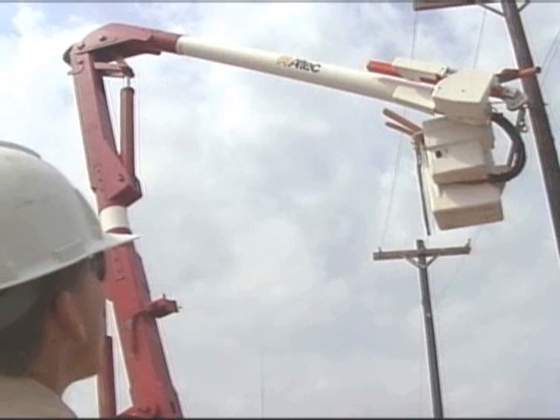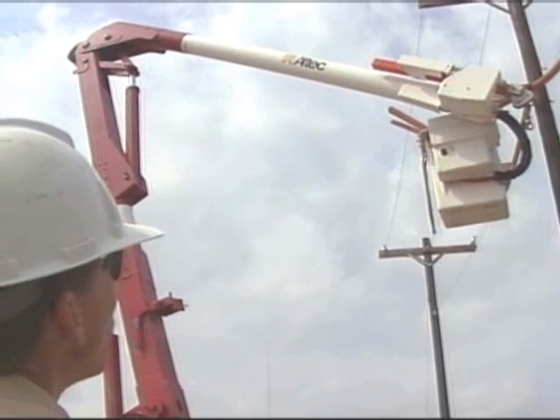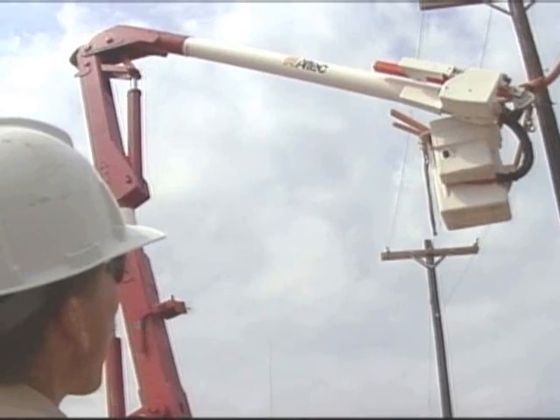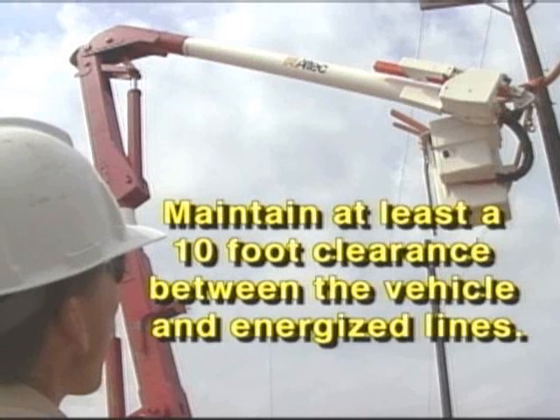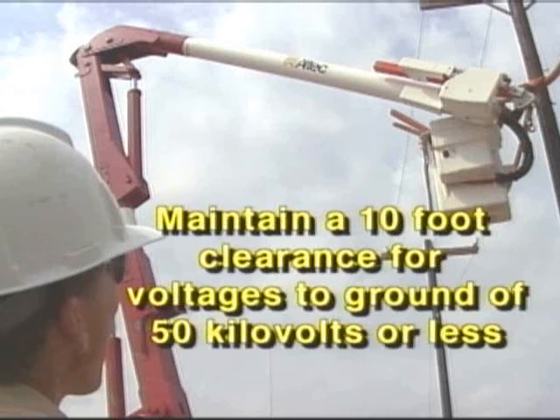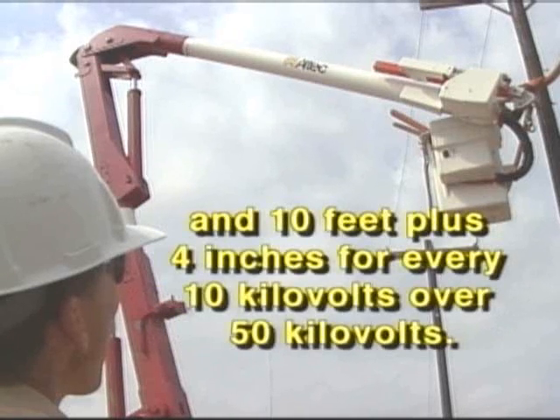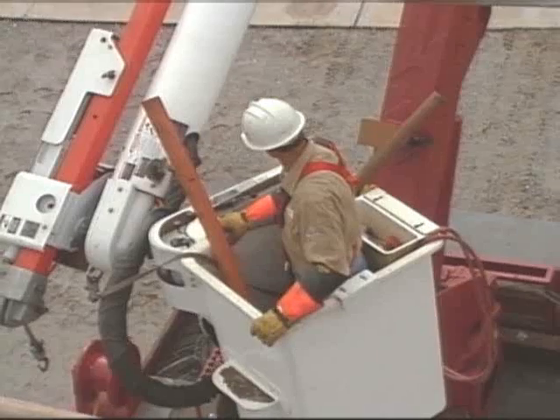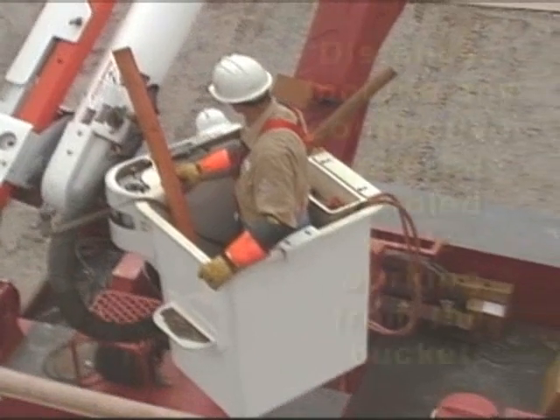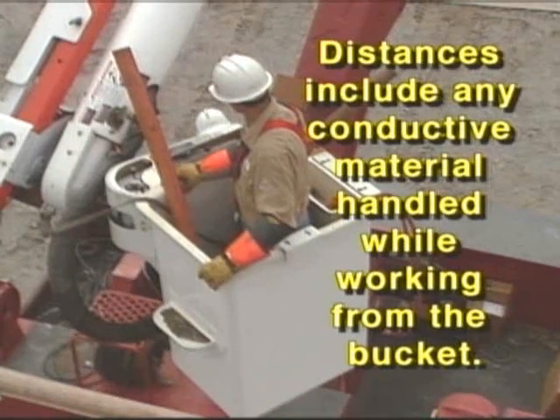Generally, you are required to maintain at least a 10-foot clearance between the vehicle, including the elevated boom and basket, and energized overhead lines. Workers who work near unguarded energized lines are required to maintain a 10-foot clearance for voltages to ground of 50 kilovolts or less, and 10 feet plus 4 inches for every 10 kilovolts over 50 kilovolts. The clearance distances required for workers include any conductive material handled while working from the bucket.